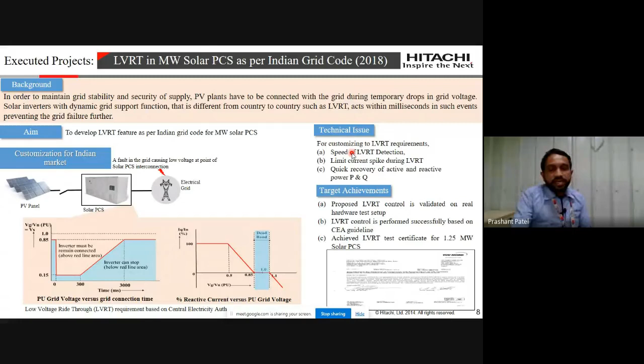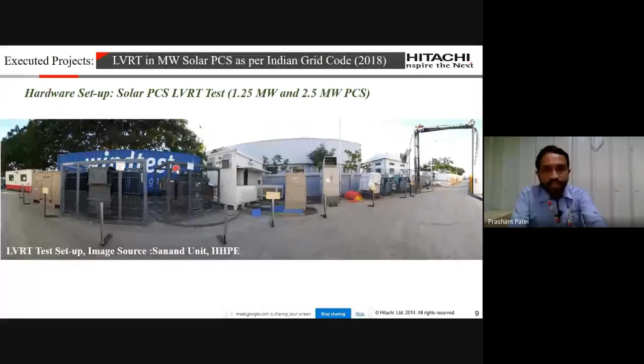For LVRT, our mega PCS is directly connected to the 11 kV supply line. Our solar PCS is situated here, connected directly to the 11 kV line through this transformer, and here in blue you can see the LVRT container. This generates different kinds of faults — line-to-line, line-to-ground, three-phase, or any fault — as part of the wind test. This certifier came from Germany, and we demonstrated our solar PCS in front of them and got the certificate.